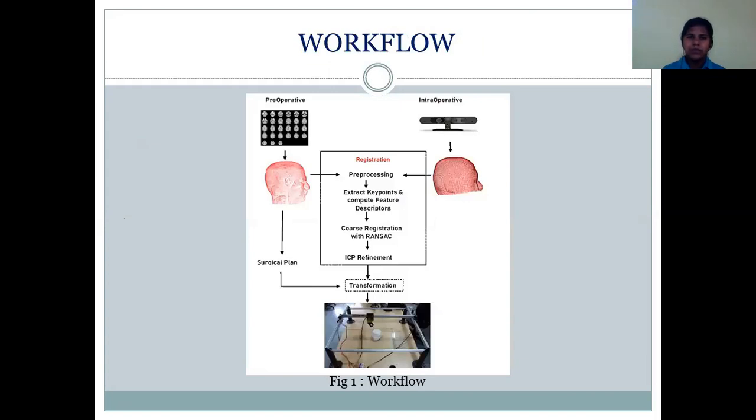This is the workflow. Images are acquired pre-operatively and intraoperatively. 3D point clouds are reconstructed from both sets of images and they are registered. The registration consists of the following steps: the two point clouds are pre-processed to match resolution; key points are extracted and described with feature descriptors; and then registration is performed in two stages — an initial coarse registration with RANSAC, which is then further refined with the iterative closest point algorithm. Once registration is complete, the transformation matrix allows any surgical plan from the pre-operative images to be transferred to the surgical table.